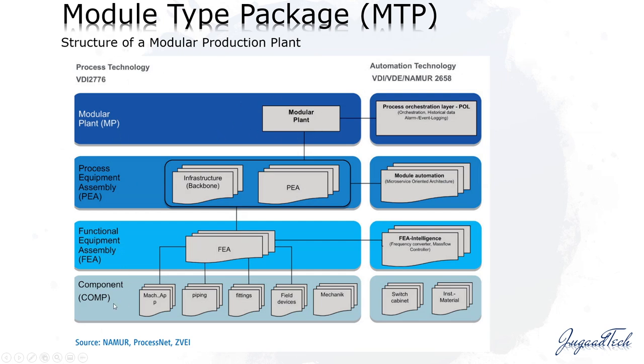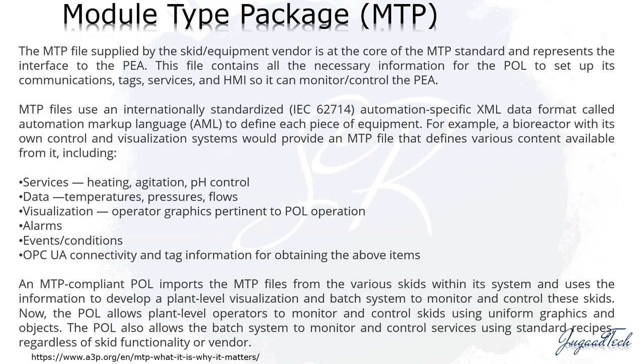The structure of a modular production plant: components are combined into a Functional Equipment Assembly, which is combined into a Process Equipment Assembly — called a PEA — with infrastructure, forming a modular plant that connects to the POL. The connection is made using the MTP file, which is based on Automation Markup Language, AML, a specific XML, to define each piece of equipment. It will have services like heating, agitation, and pH control loops; data like control modules sending process values; visualization including graphics, alarms, and events; and OPC UA connectivity.